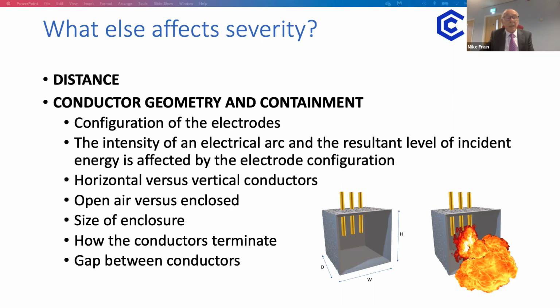There's also the open arc versus an enclosed arc. On the right-hand side, you can see an enclosed arc and roughly what the test setup looks like. In that particular case, that's called a VCB type of arrangement, and the conductors are vertical. That's why they're mentioned as vertical, and you can see that the actual thermal energy is forced downwards and out towards the worker in more intensity than you would in an open arc system.